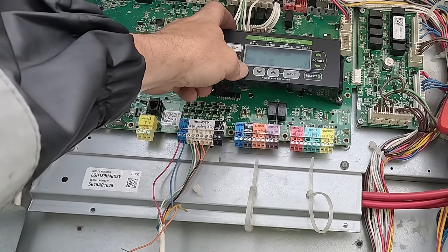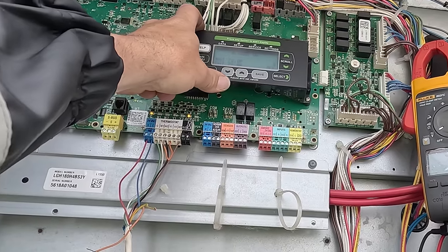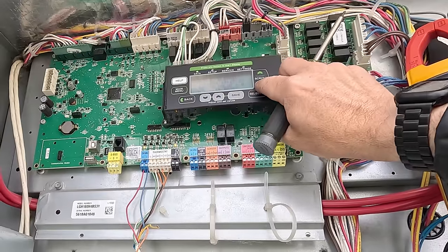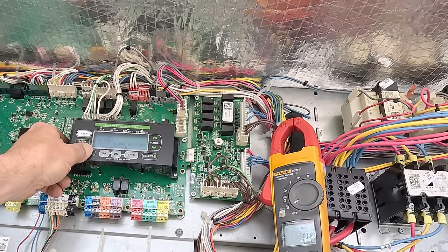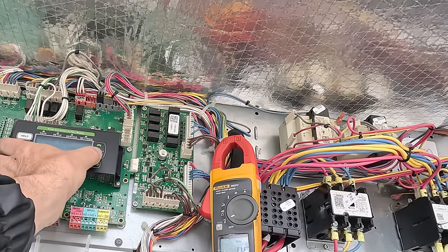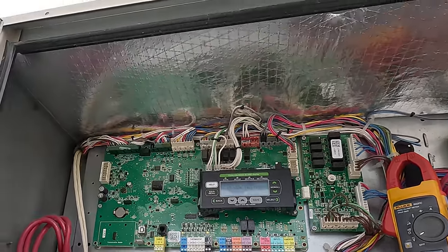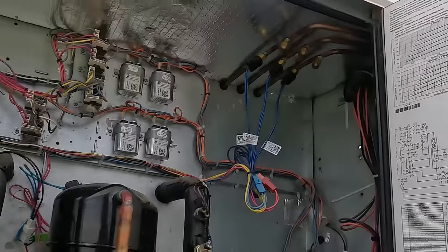Let's go to the main menu, see if there's anything we can see here. Blower on, show status, see what data is there. Select, return error, discharge error. Alarm 82 cleared 515. Today is 515. Alarming valve equals zero. Controller reset. Neither up nor down really works there. Okay, go back. Last service, select. No service event. History, back. That's it. So under alarms, it only has one, alarm 82. Alarm 82 means don't worry about it, okay?